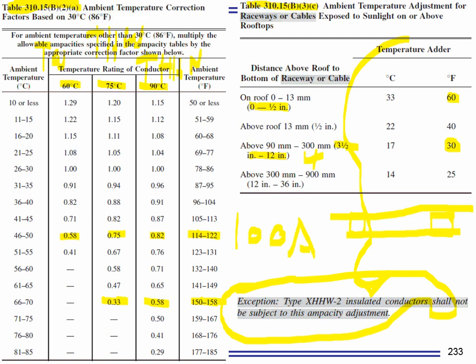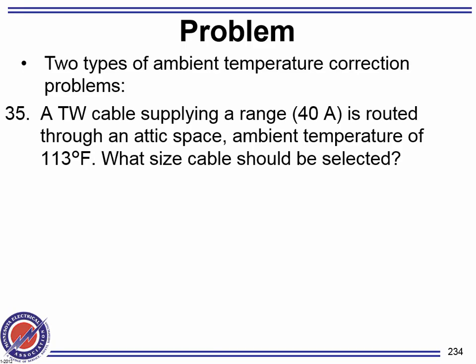Yeah, I see the confusion. If it's bundled, you derate. If it's at another temperature, you derate. You just don't add more temperature on and off only. Okay, gentlemen, we have a TW cable supplying a 40 amp load in the attic, and the ambient temperature is 113. What size cable should we use?